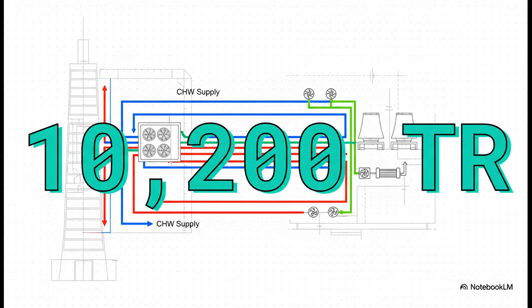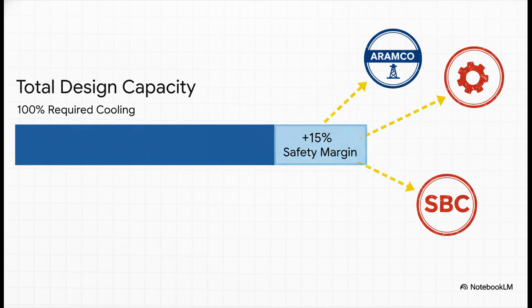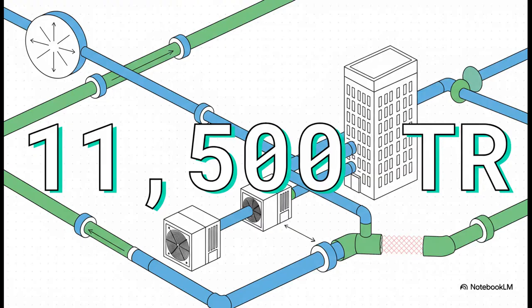And just to give you some perspective, 1 TR is the amount of energy it takes to melt a ton of ice in a day. So yeah, that is a staggering amount of heat we need to remove. But wait, we can't just stop there. We can't design the system to just barely meet the demand. Codes like the Saudi Building Code and major engineering standards from places like Aramco are super clear about this. You have to add a safety margin, usually around 15%, to make sure the system can handle the hottest days and has room for the future. So we add our 15% safety margin, and we land on our final design capacity, 11,500 tons of refrigeration. This is the number.